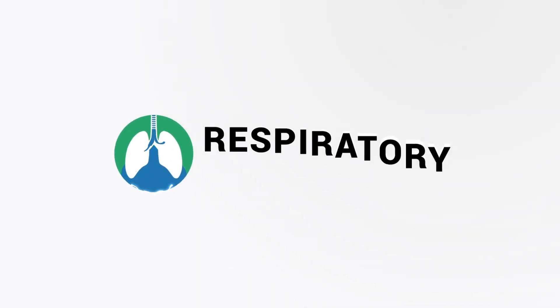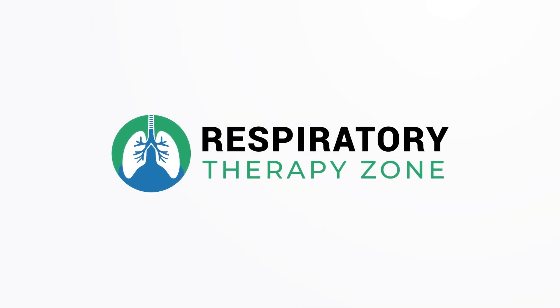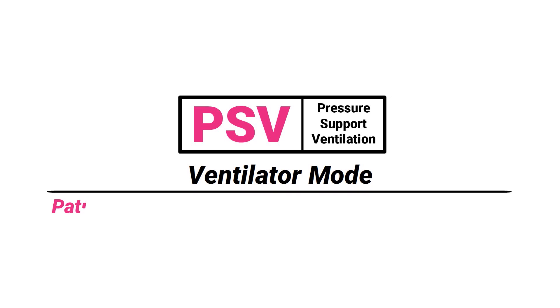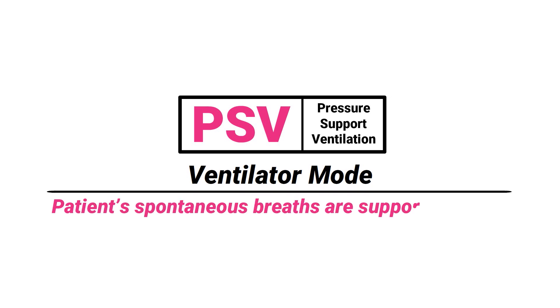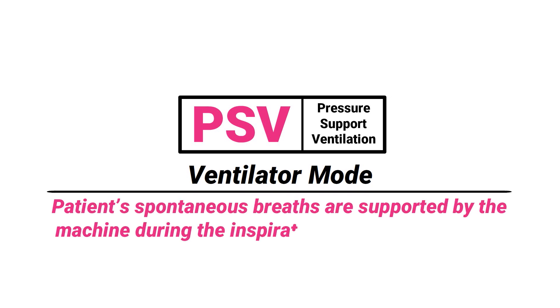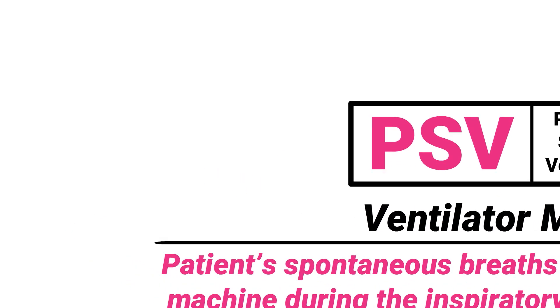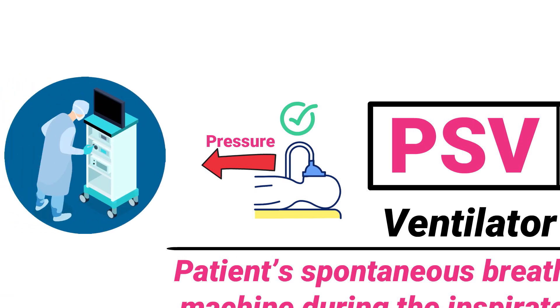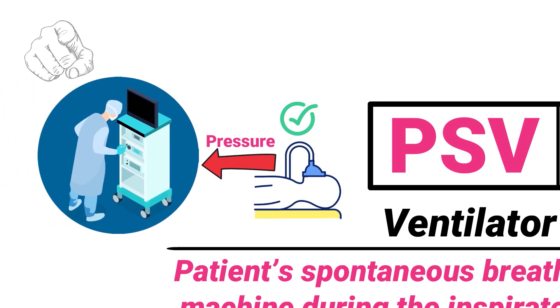PSV, or pressure support ventilation, is a ventilator mode in which the patient's spontaneous breaths are supported by the machine during the inspiratory phase of breathing. As the patient triggers a breath, the ventilator assists by adding pressure to make breathing easier. The level of pressure is preset by the operator, which means that you have control over how much support the patient is given.